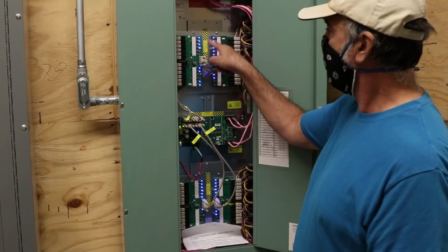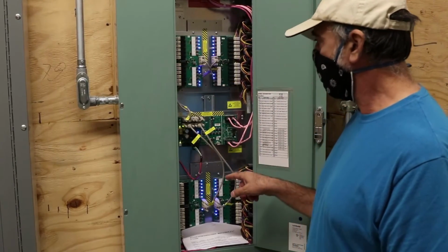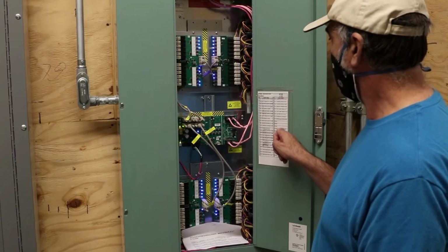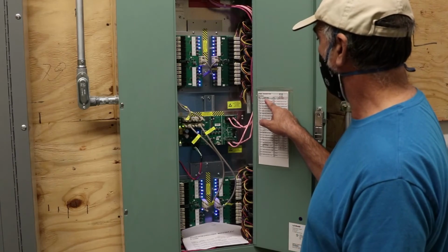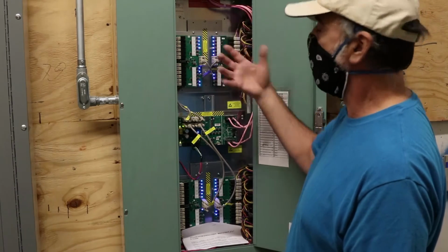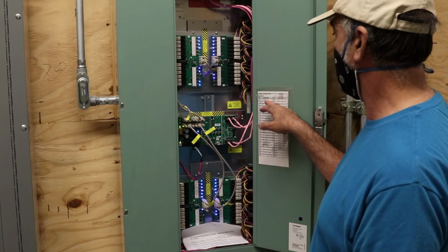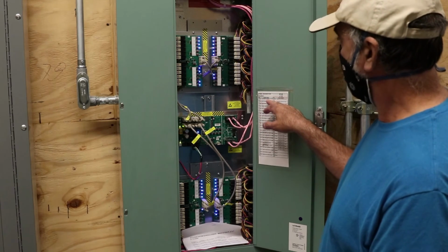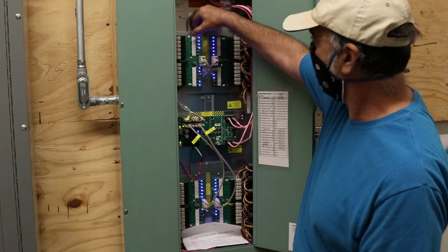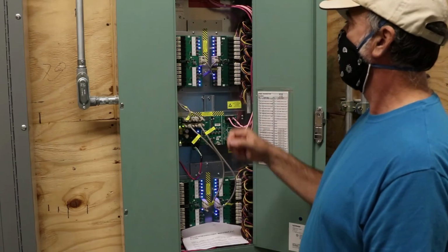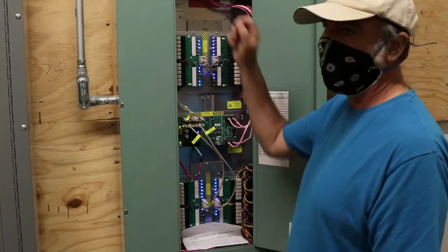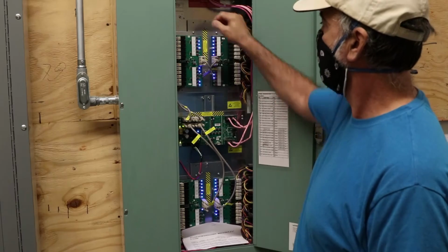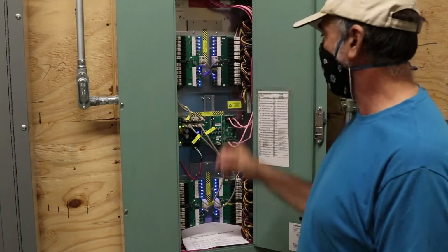The blue lights here indicate which relays are on. And there's a schedule here that would tell you what they are. You can manually turn off a light, or maybe you want to test a light. Like this first one here is the corridor general lighting. I could actually press this. You hear a click, little light goes out, the relay opens. Wherever that corridor is, lights just turned off. So you could test lights from within the panel.